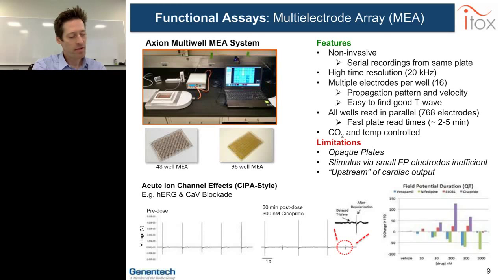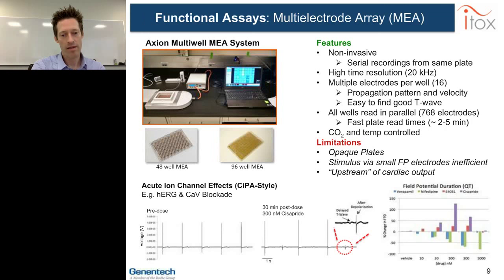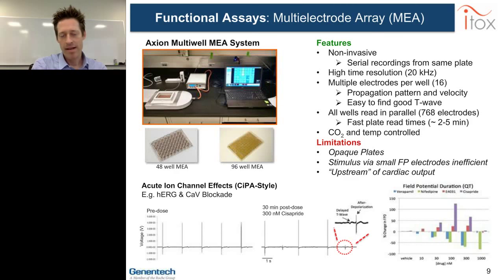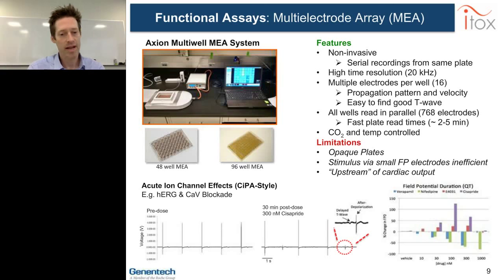The system we use most here in-house is the Axion multi-well MEA system. MEA systems have been around for roughly four decades, but Axion has turned this into a legitimate multi-well platform. The system is small for a plate reader, environmentally and temperature controlled. We use a 48-well plate where each well has 16 non-invasive field potential electrodes in a 4×4 grid. A strong advantage is that because the electrodes are non-invasive, you get serial recordings from the same plate — we can record from this plate every day for a month if needed. The system samples at 20 kHz, giving fine resolution of depolarization features.